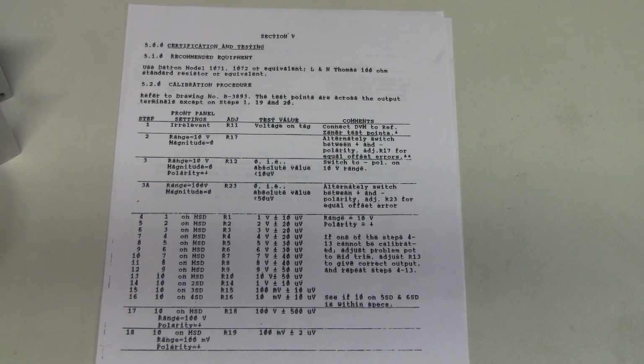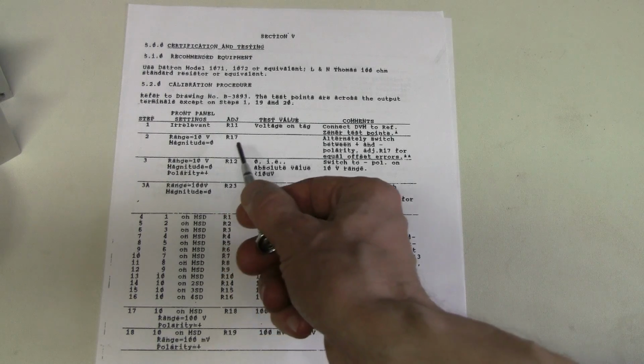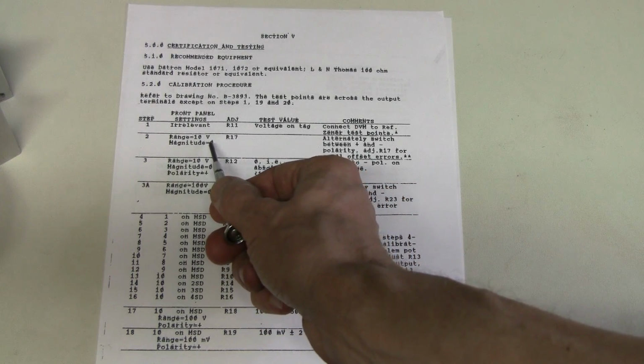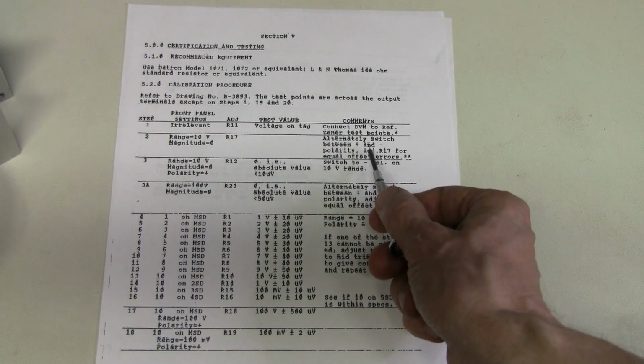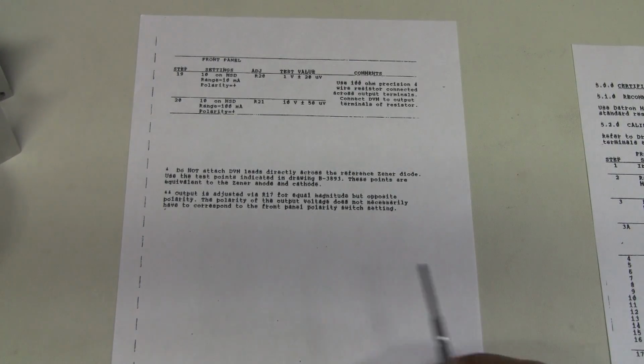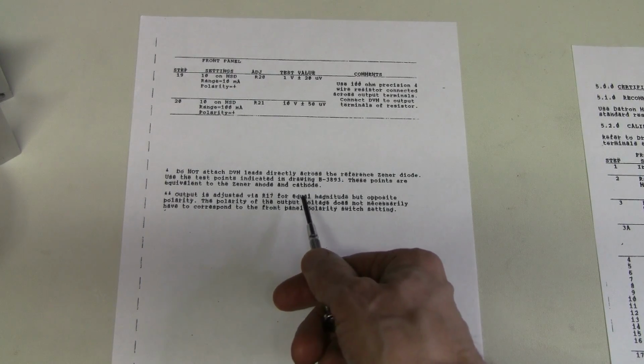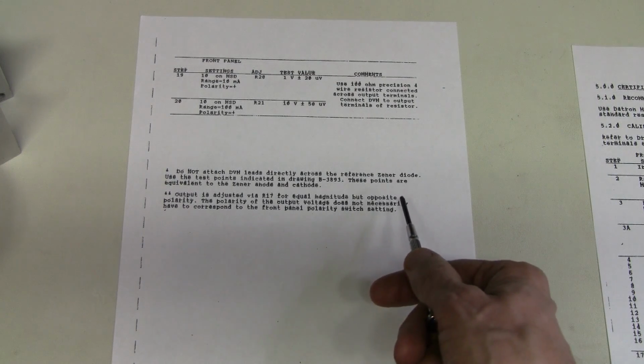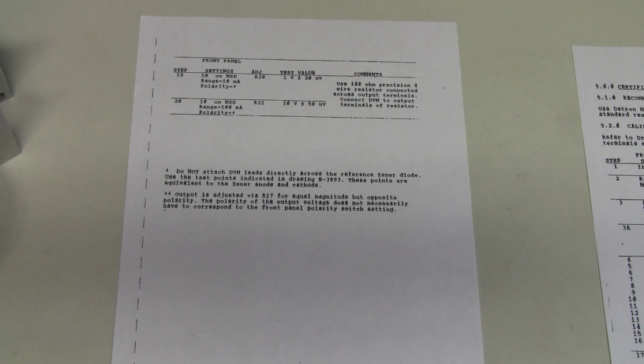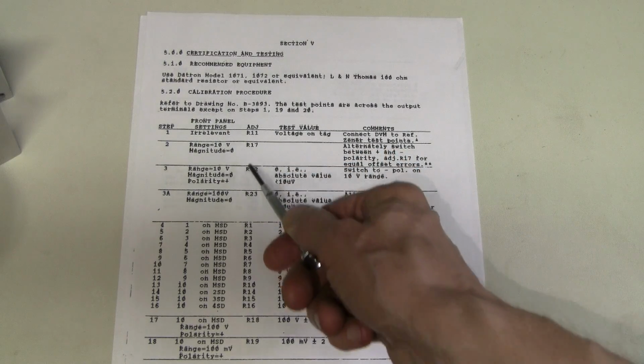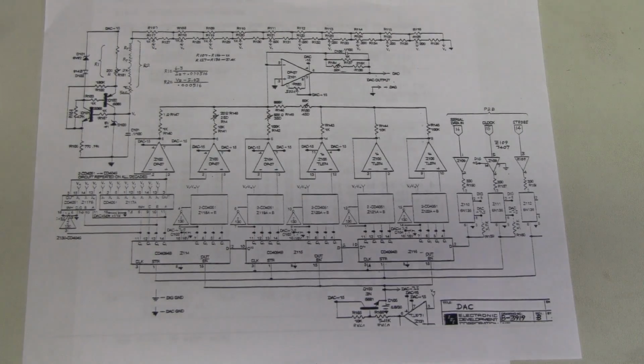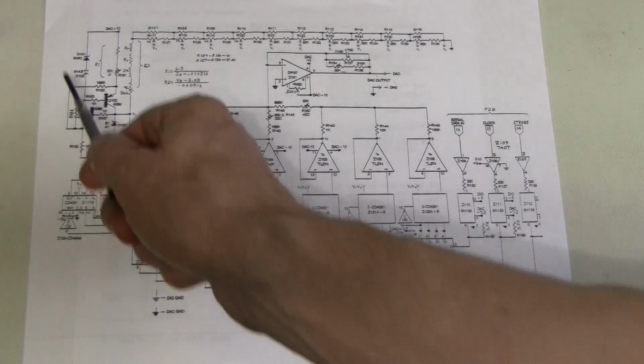Here is the adjustment procedure, and the second step here is precisely about this 0 point of the amplifier. At 0 setting and 10 volt range, we are supposed to switch the polarity back and forth and adjust R17 so that the magnitude is the same but the polarity is opposite. Here is a note about that. R17 is adjusted for equal magnitude but opposite polarity. But we have the same polarity. There is a problem with this adjustment procedure though. I don't see these designators on the schematic at all. Here is the schematic for the DAC, and this is the reference circuit.